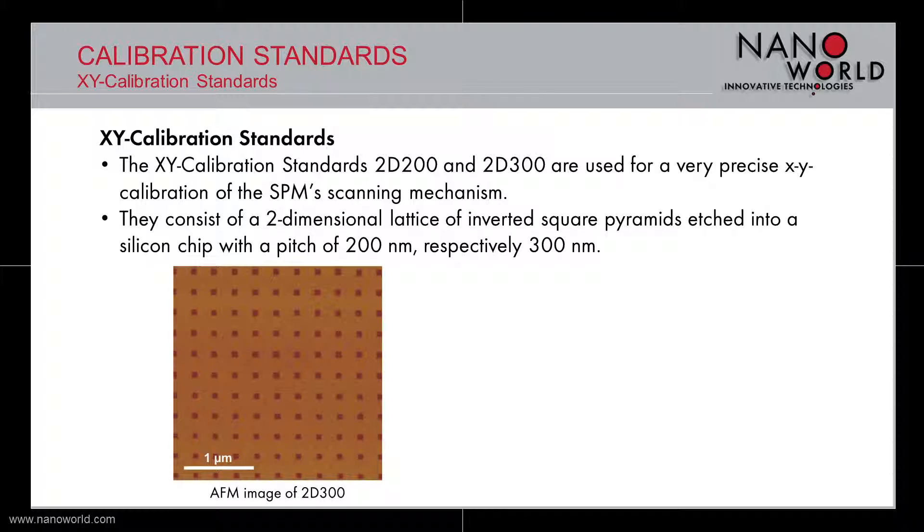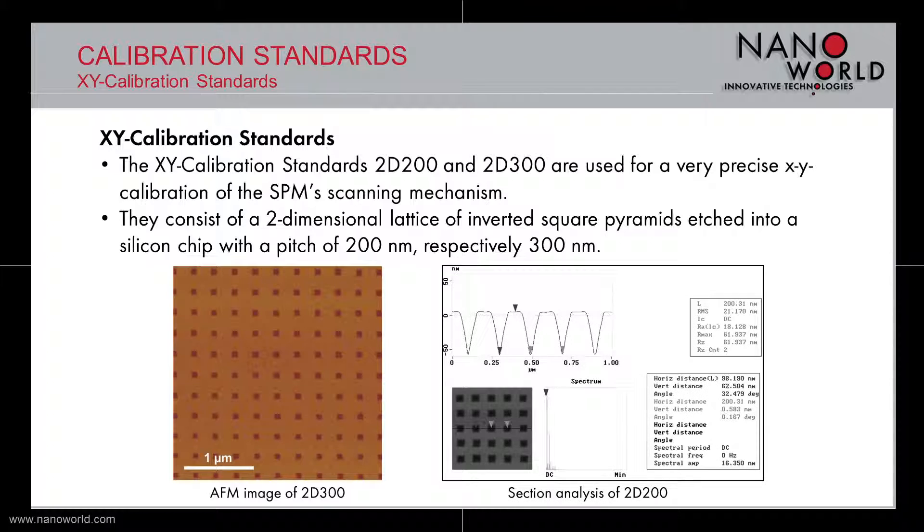On bottom left you can see an AFM image of the calibration standard 2D300 on which you can observe the squares which are the basis of the inverted pyramids etched into the silicon.